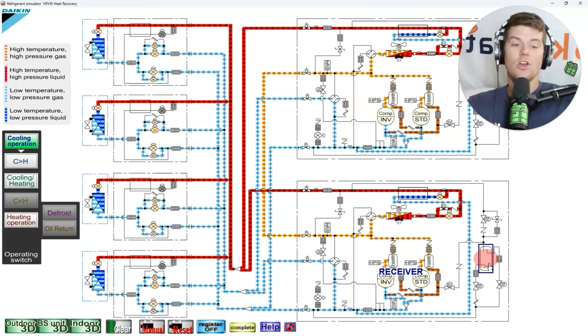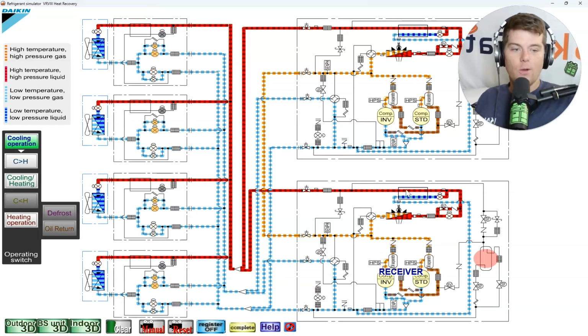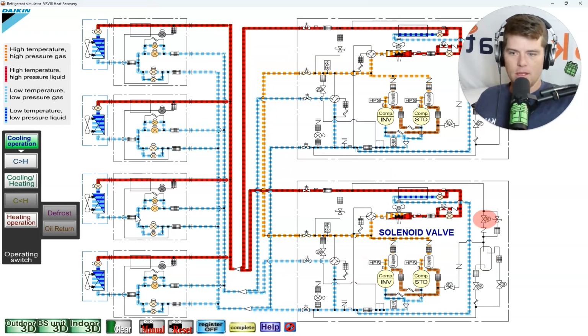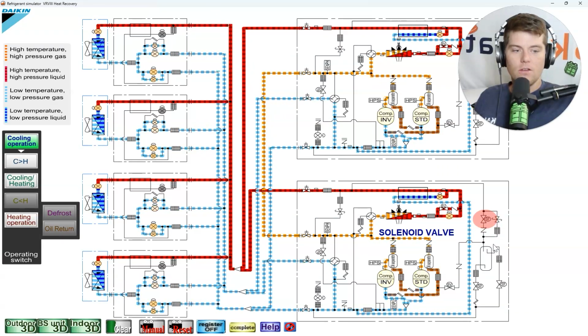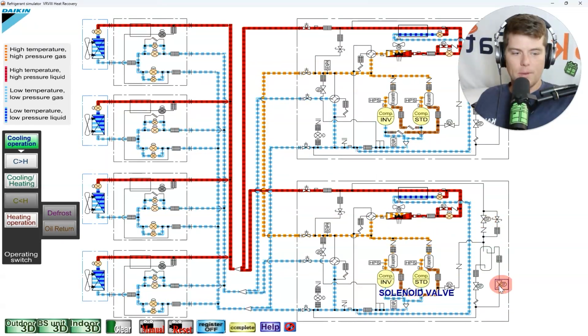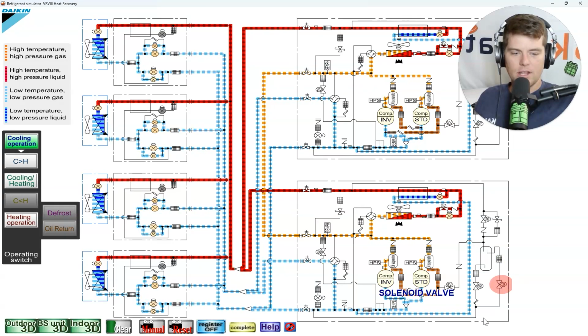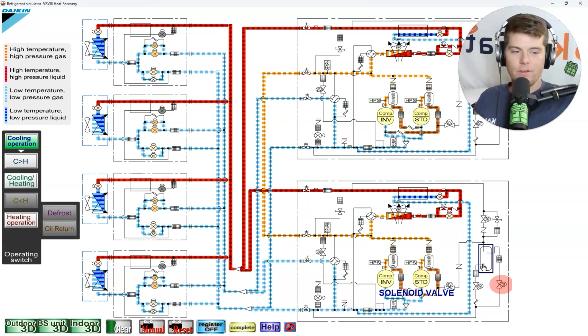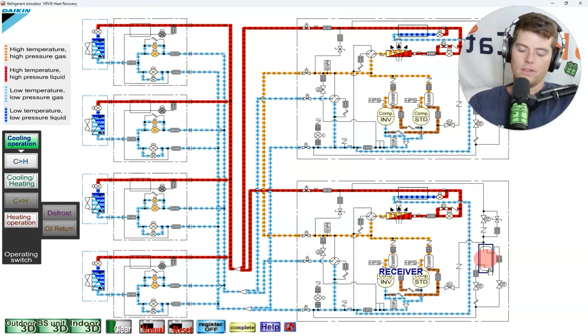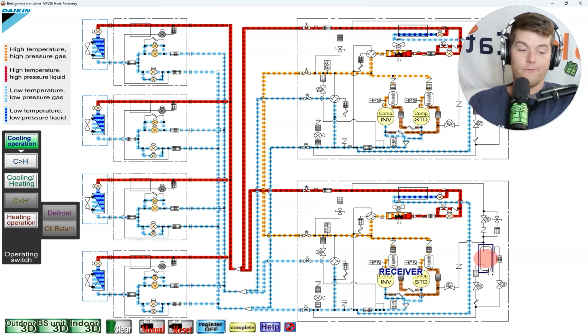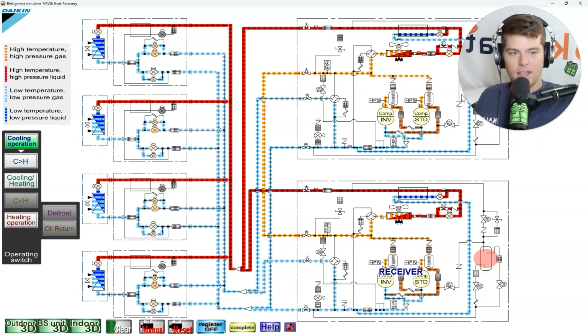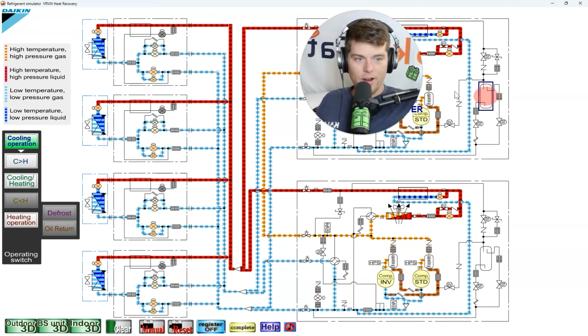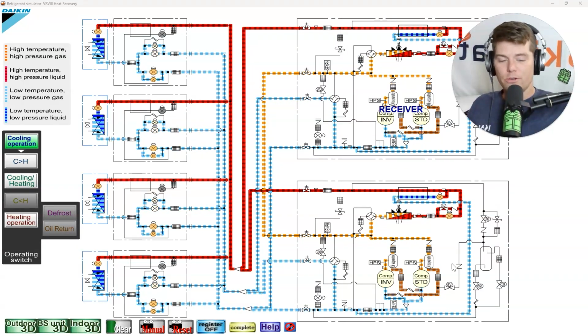With VRF systems, we stack the liquid refrigerant in the liquid receiver. On VRV3, it was completely separated from the liquid line. And what happens is the solenoid on top opens up, right? We pull liquid into the top of this tank. At the same time, we then open this one up here. We purge the gas out of the top of this tank, back over into the suction line, and it fills this liquid receiver. In the process of filling this liquid receiver, we now pull the refrigerant from the actual system and stack it in this tank. And we can do that in both modules. We have one here and we have one here. That allows us to pull liquid refrigerant away from the system.